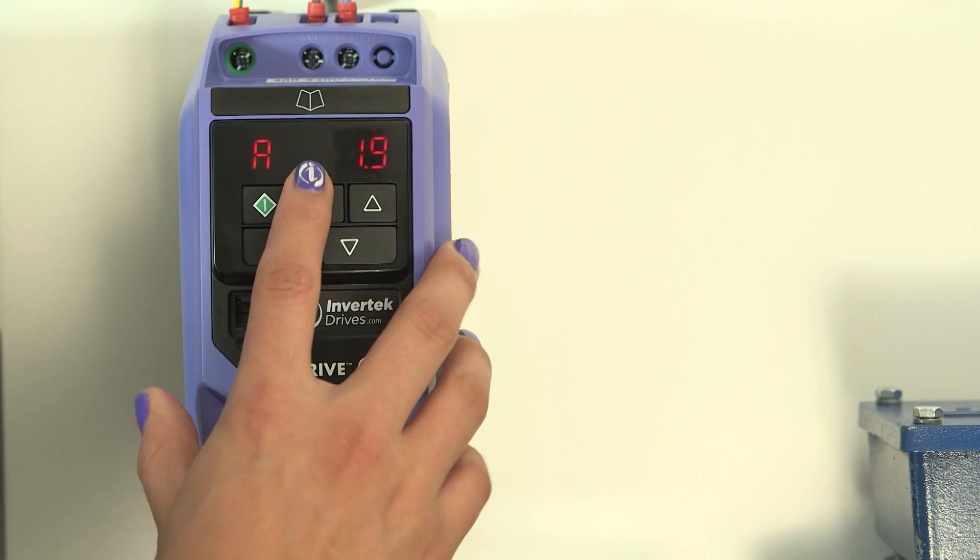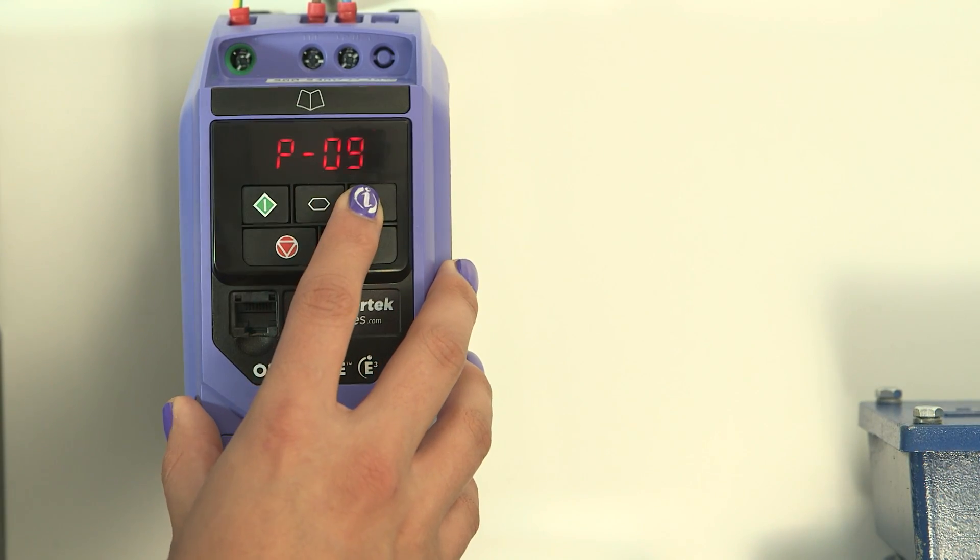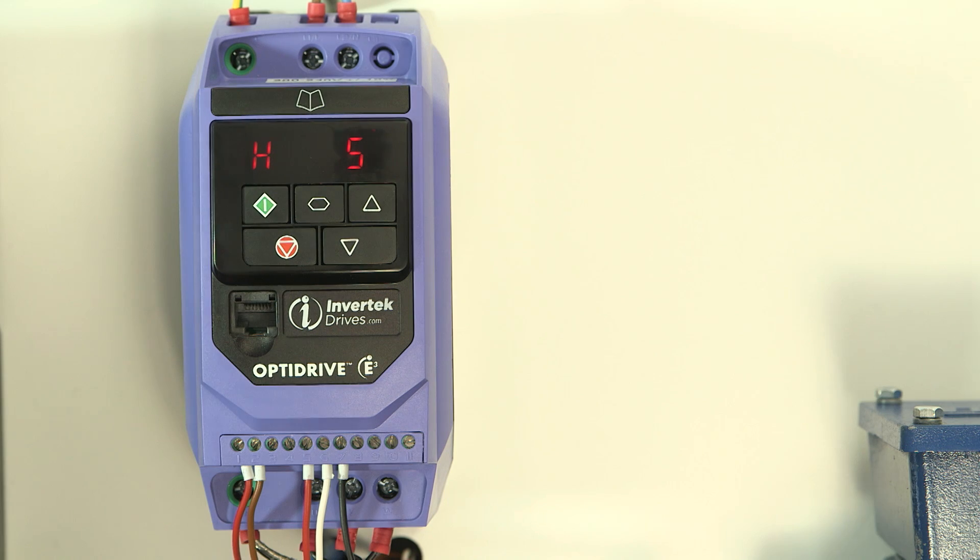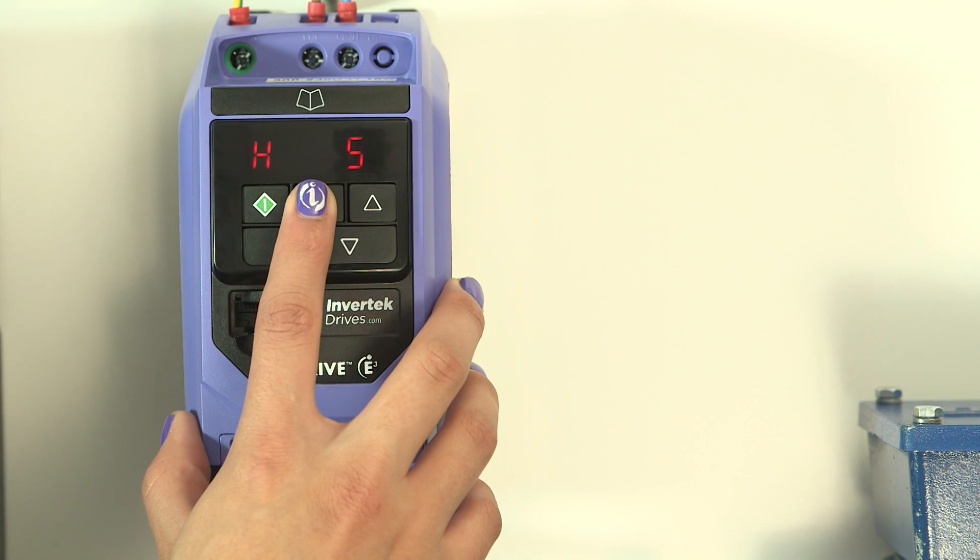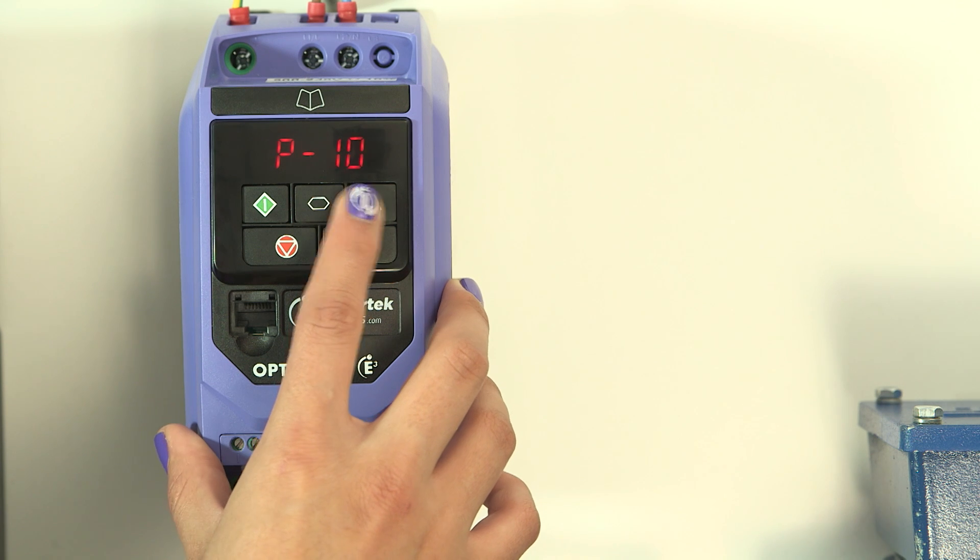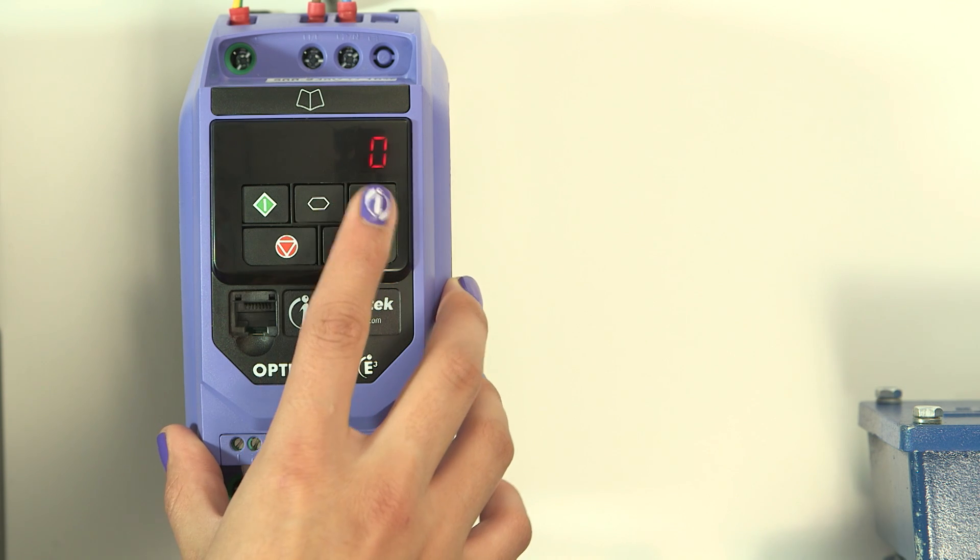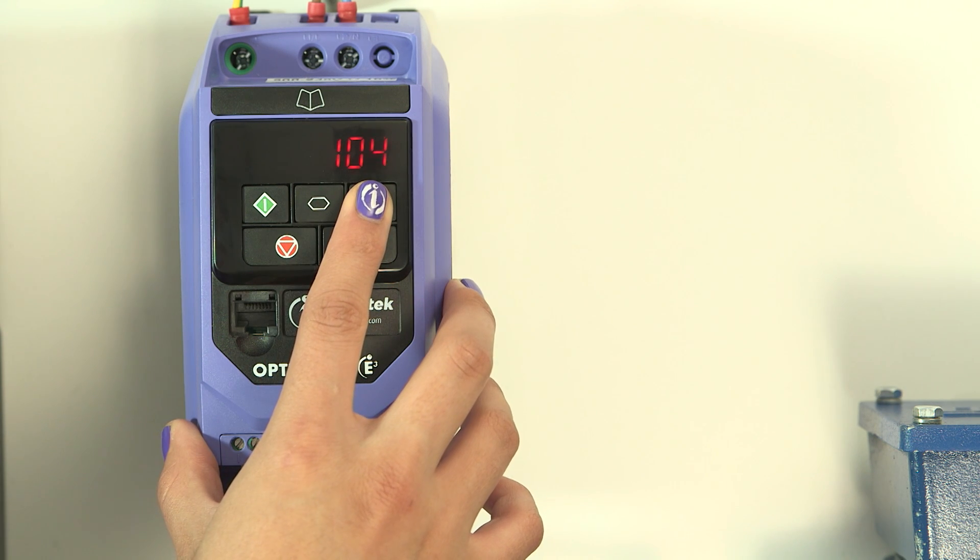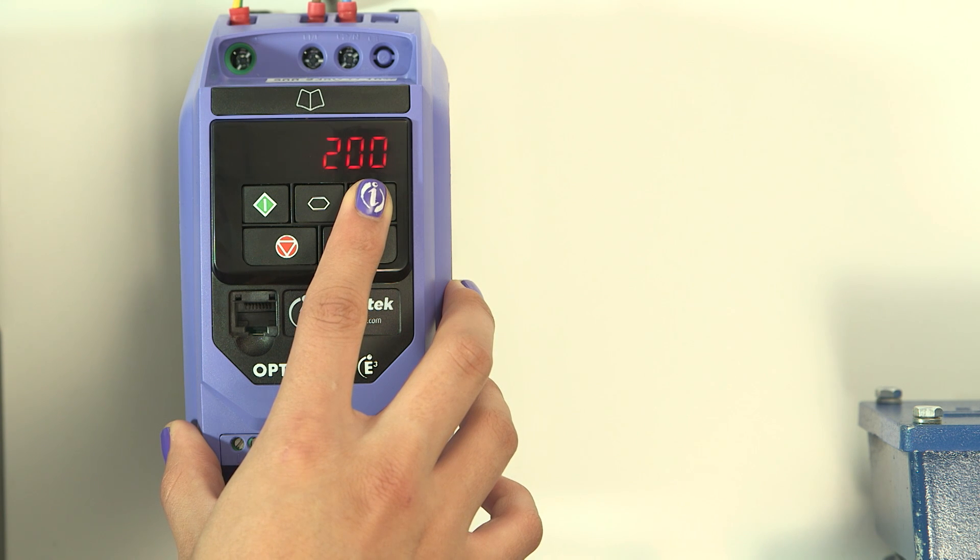Press navigate and scroll to parameter 9 which is the motor frequency. This already matches the motor so we don't change it. Now go to parameter 10 which is the motor RPM. If I change this from 0, the main effect is to change the display to RPM. I will set it to what's on the motor rating plate, 1400.